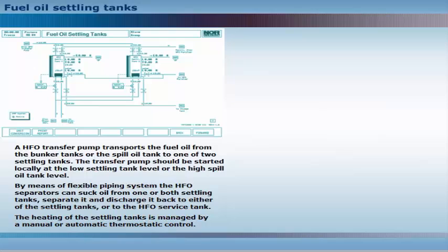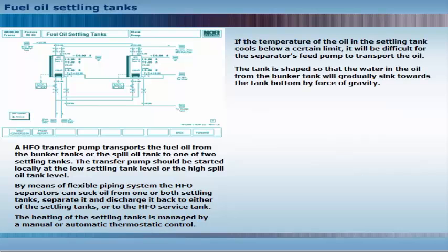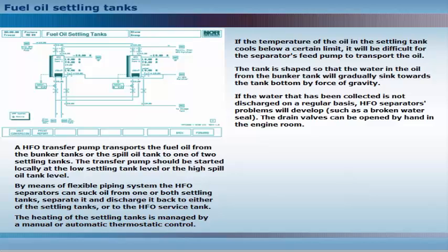The heating of the settling tanks is managed by manual or automatic thermostatic control. If the temperature of the oil in the settling tank cools below a certain limit, it will be difficult for the separator's feed pump to transport the oil. The tank is shaped so that water in the oil from the bunker tank will gradually sink towards the tank bottom by force of gravity. If the water that has been collected is not discharged on a regular basis, heavy fuel oil separator problems will develop, such as a broken water seal.